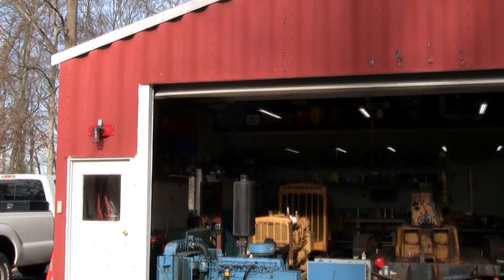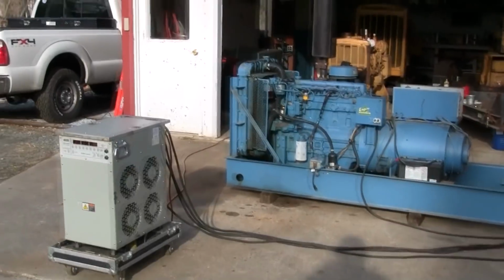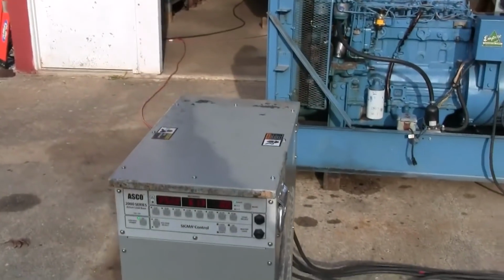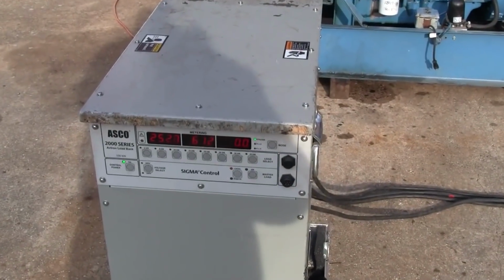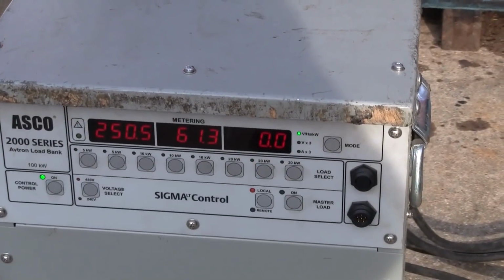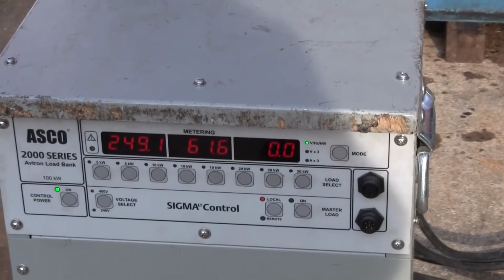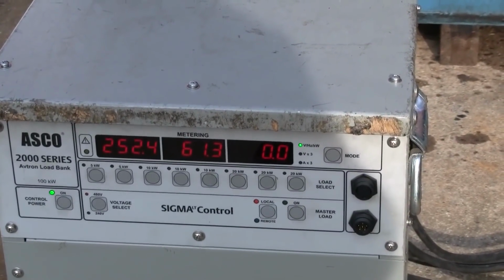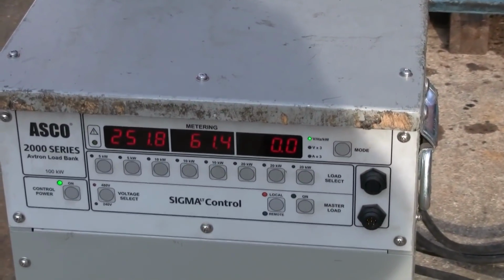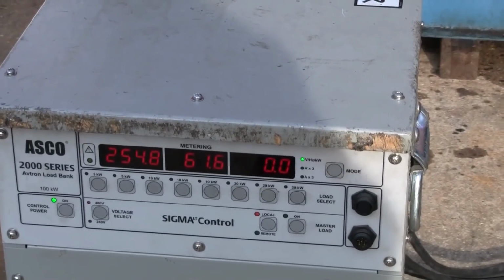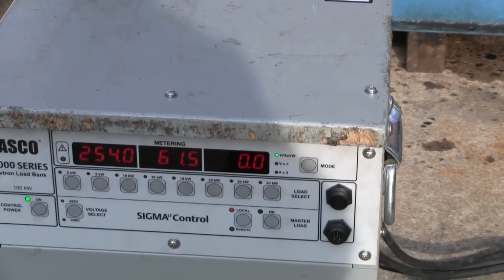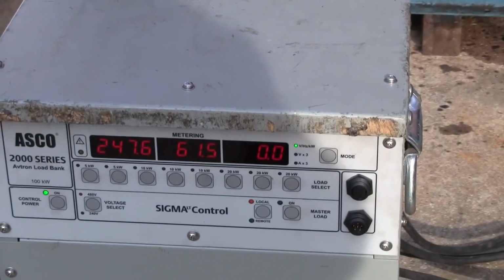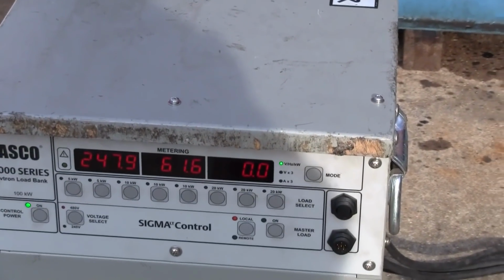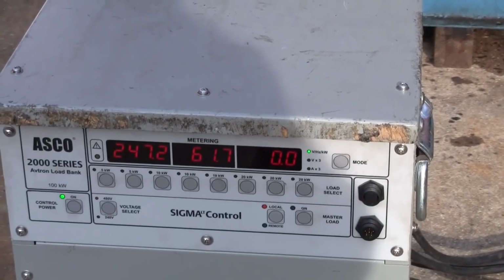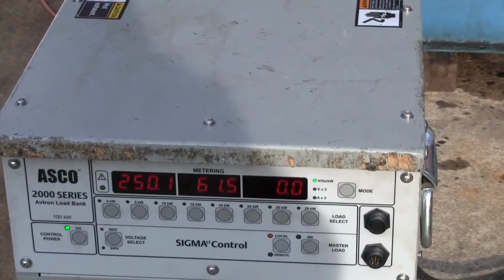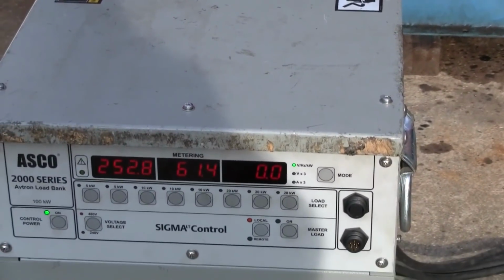Got a little bit of blue smoke here, still warming up. Let's go over to the load bank. So with no load, we're at about 61.5 hertz, we'll call it. You'll notice the voltage bouncing around quite a bit. Look at that, 256, 254. That's my second issue with this unit. That Empire brand voltage regulator does not seem to be doing its job all that well. You got a little bit of flutter in that voltage at no load and at load. And there's no stability adjustment on that regulator either. It's only voltage level. Chances are that could be repaired, probably just some dried out capacitors in it, but I think it's time for an upgrade nonetheless.